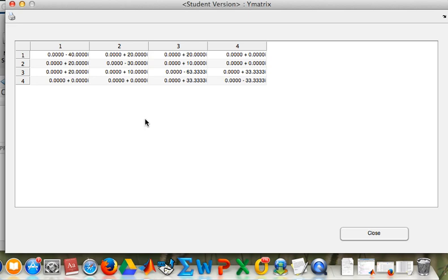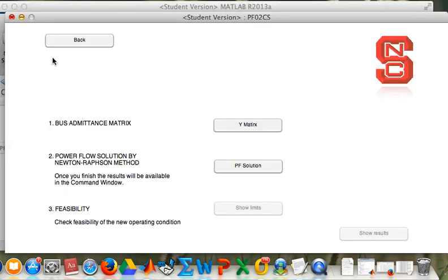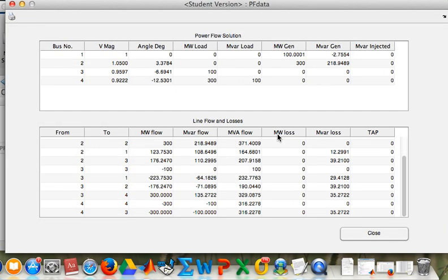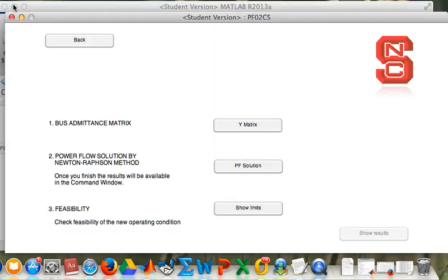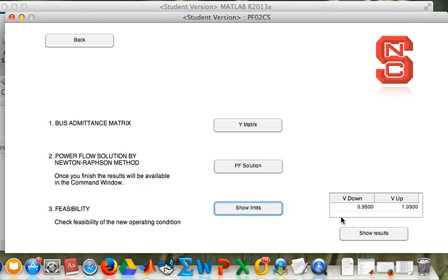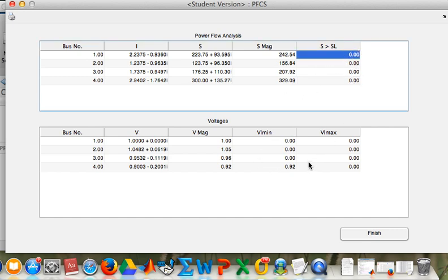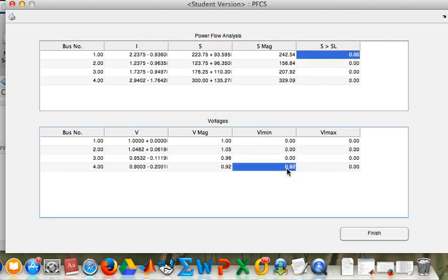So this is the new admittance matrix. This is the power flow solution. Again, the analysis will be specified in the report. This is the limits configured previously, and we are seeing just one violation.